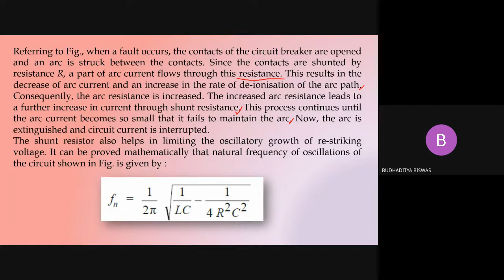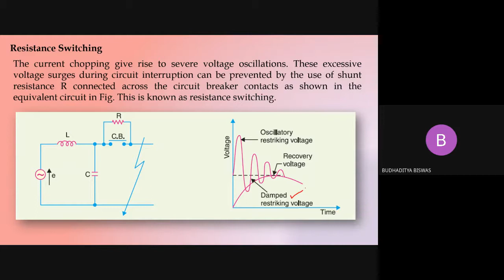The effect of shunt resistance R is to prevent the oscillatory growth of the restriking voltage, and in case it is to grow exponentially upon recovery voltage. So you see, we make the system critically damped. Critically damped means this is the oscillatory restriking voltage, and due to this unwanted oscillation, some arc will be destroyed. So we try to make the system in such a way where the critical damping is there. It will start and ultimately reach the recovery voltage. And if we are able to do this, there is no such oscillation, and the restriking voltage is not able to make any restrike of the arc. So this is a damped restrike voltage, and this damping is only possible if we put a resistance across the circuit breaker contacts.